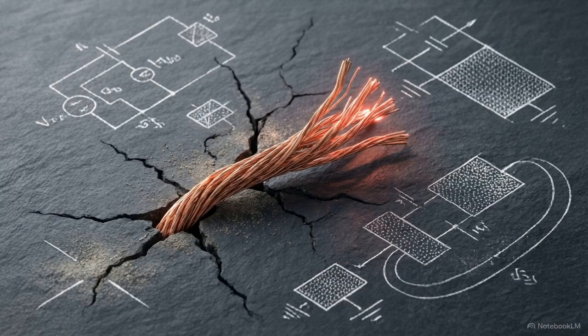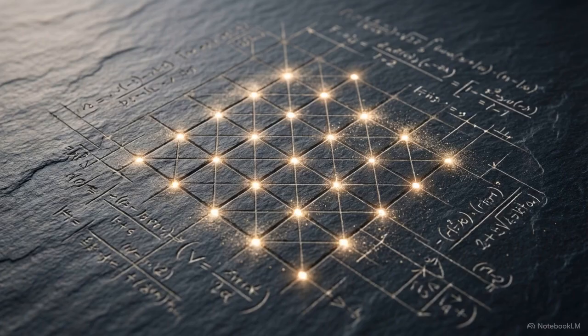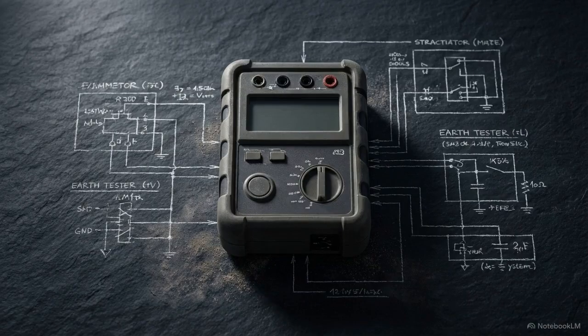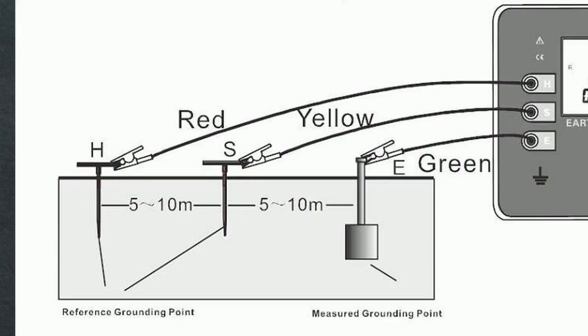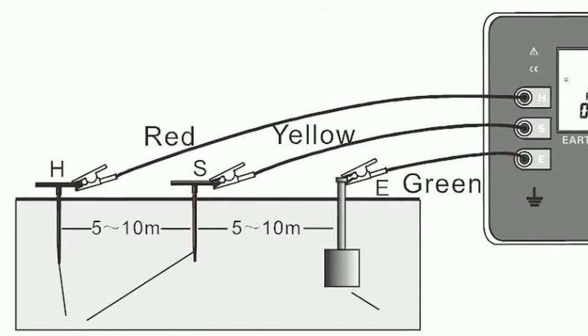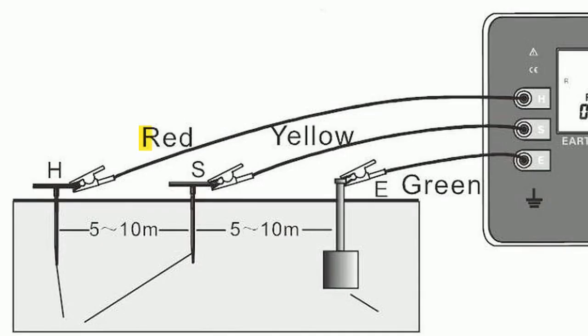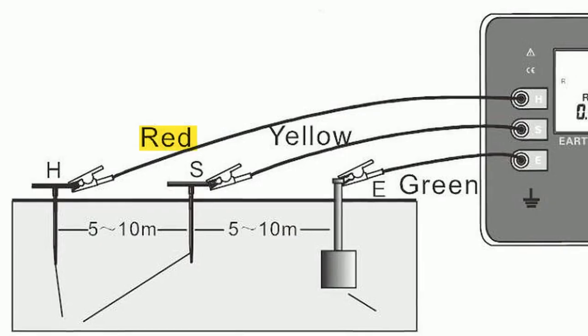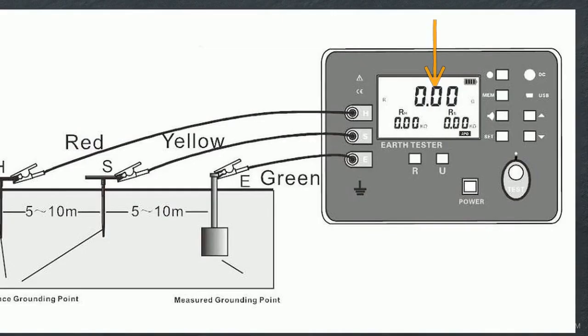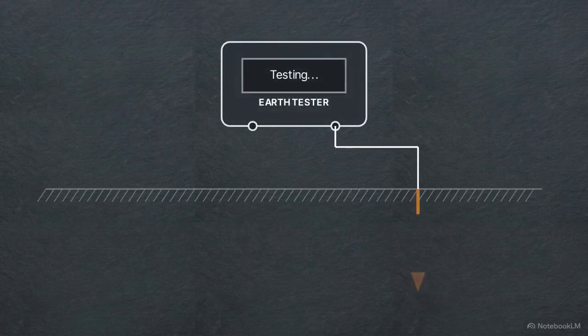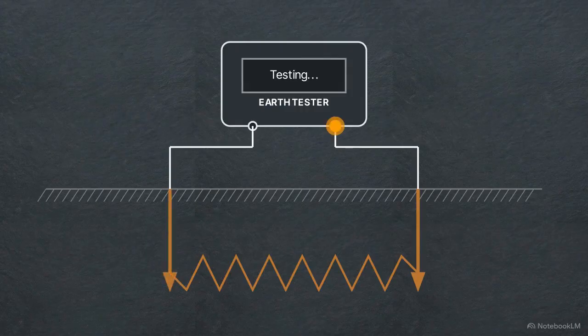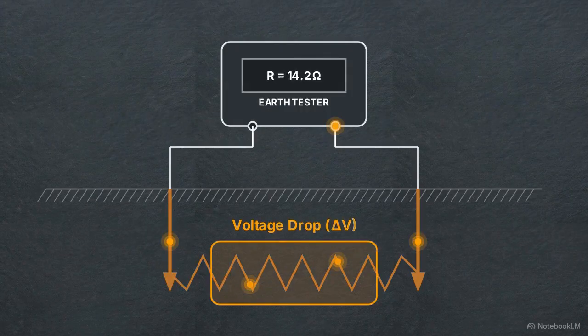Burying a conductive wire in the dirt does not guarantee a functional safety pathway. The actual electrical resistance of the surrounding soil environment must be precisely measured and quantified. To verify this, engineers utilize a specific diagnostic instrument known as an earth tester or earth meter. The earth tester uses test probes driven into the ground at points H, S, and E, separated by exact 5 to 10 meter gaps. Current injected through the red and yellow lines meets Earth's resistance, producing a measurable voltage drop registered on the device. By executing this test, the meter effectively incorporates the raw ground into a temporary circuit, allowing us to quantify its hidden conductive properties.